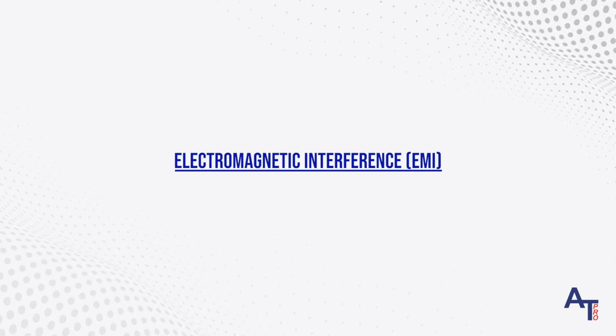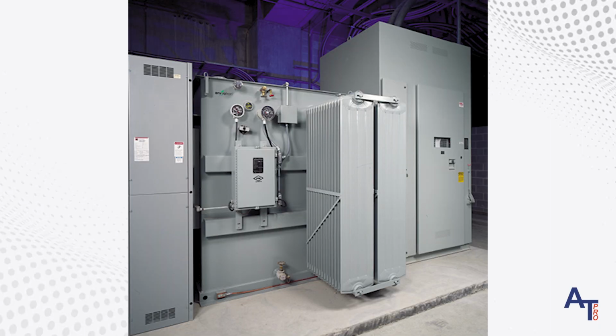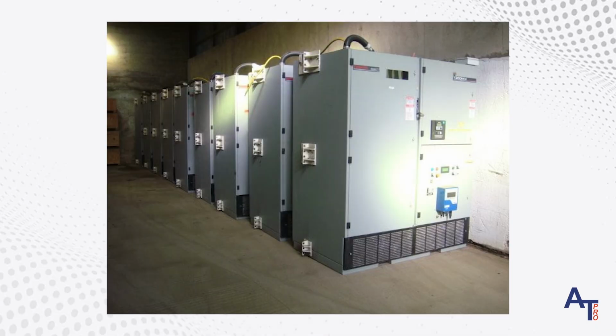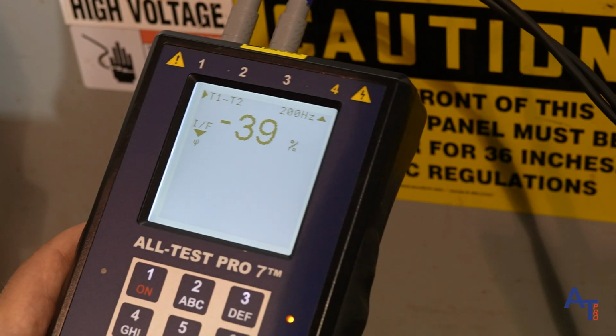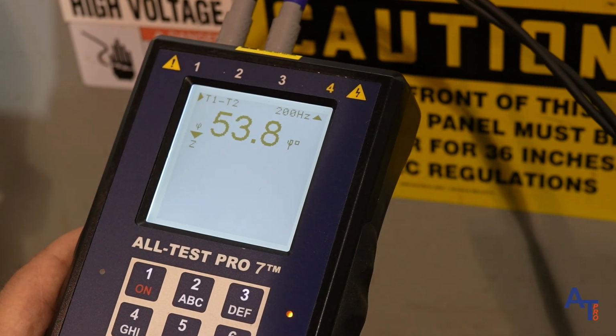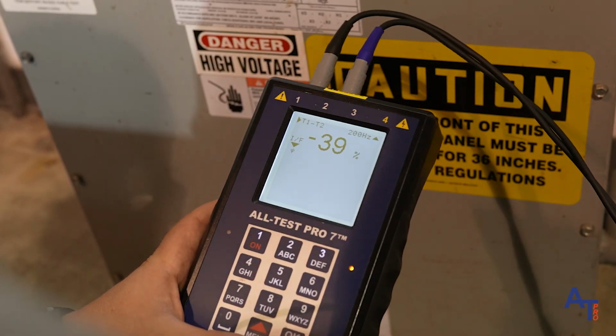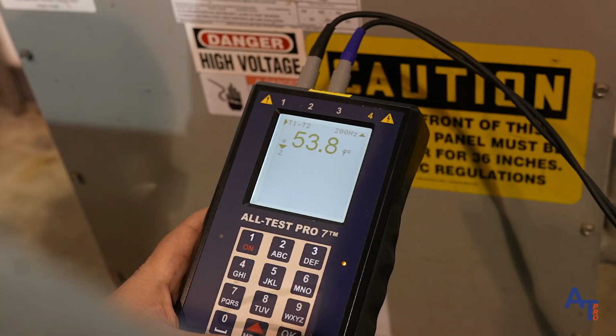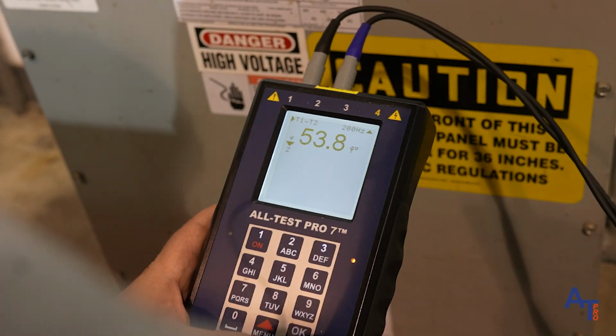Electromagnetic interference, EMI. Nearby inductive loads like transformers or AC controllers can distort readings. The real-time test reveals EMI through flickering or cycling values, allowing technicians to isolate the interference or relocate the motor for accurate testing.